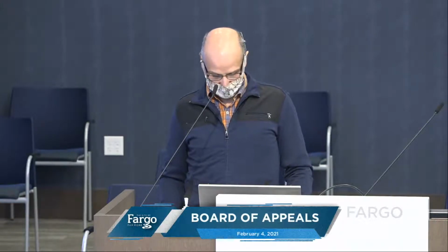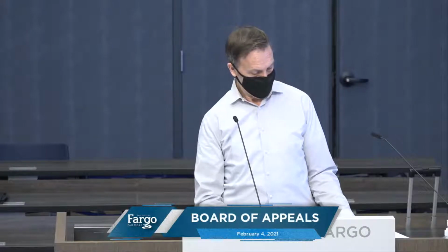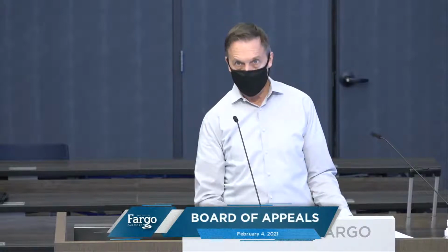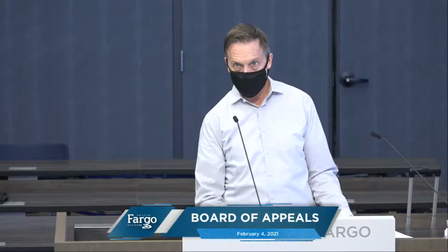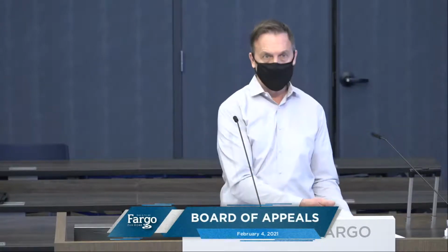Thank you. Let's just go with 508. I'm going to read footnote B again from the commentary. The fire rating of a space used solely for private or pleasure vehicles may be reduced by 1 hour, but never less than 1. Never less than 1. It's anticipating this. It didn't say it's 1, 2, 3, or anything. Never less than 1. It says it. It's clear. We interpreted that before we looked at this book.